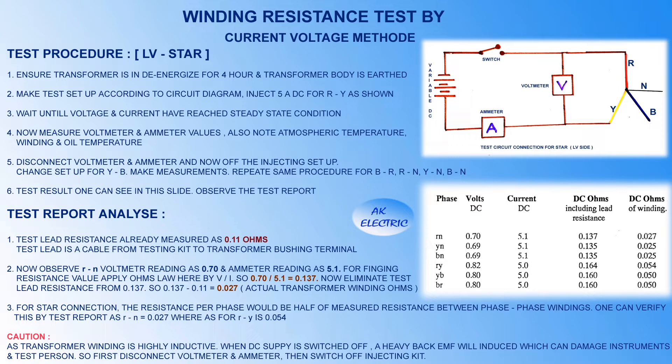Likewise we have to measure all other connections: Y-to-N, B-to-N, R-to-Y, Y-to-B, and B-to-R. For star connection, the resistance per phase is half of the measured resistance between phase-to-phase windings. One can verify this in the test report: R-to-N is 0.027 ohm whereas R-to-Y is 0.054 ohm.